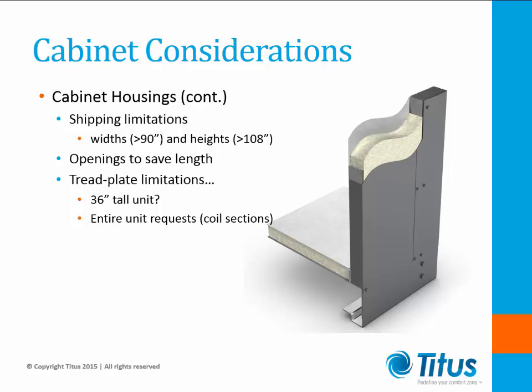The width is not the only item to take into consideration on a cabinet. Avoiding cabinets taller than 108 inches is also required. Overheight shipping charges begin when total height is over 120 inches. Total height includes base rails, top dampers, and discharge flanges from different fans within the unit.